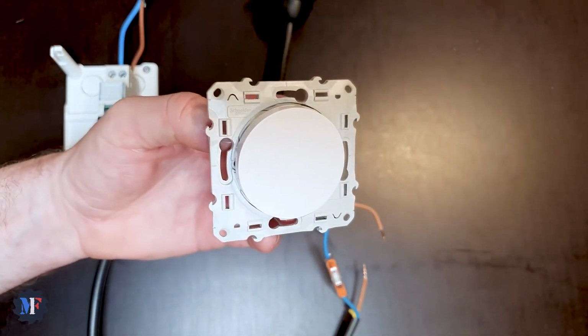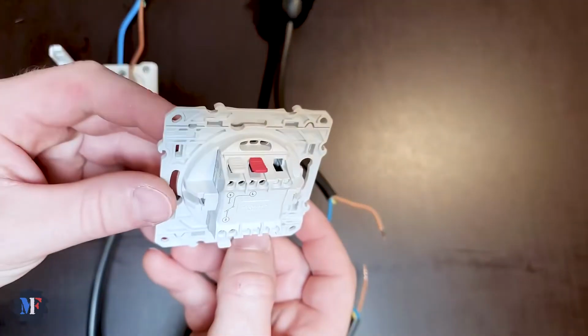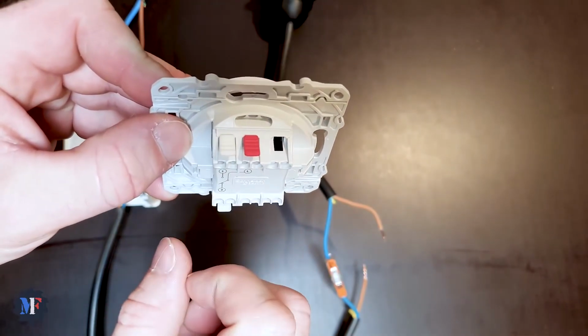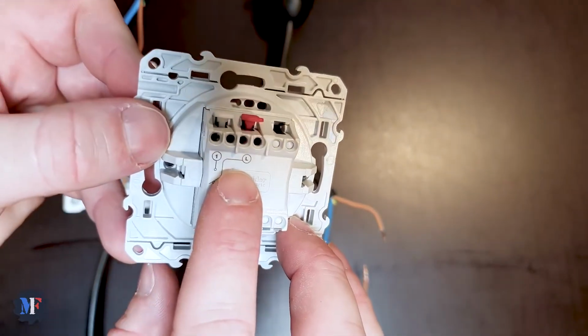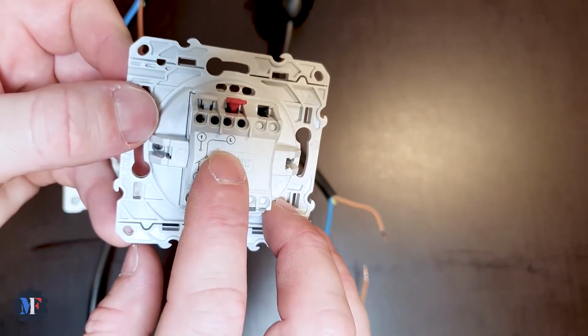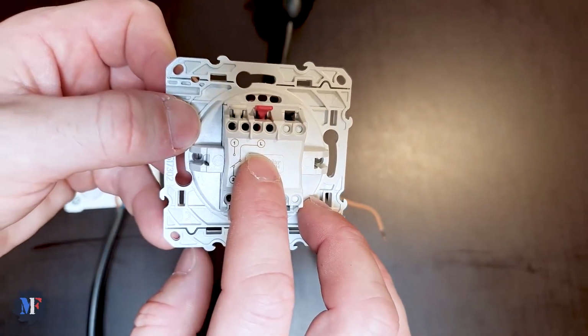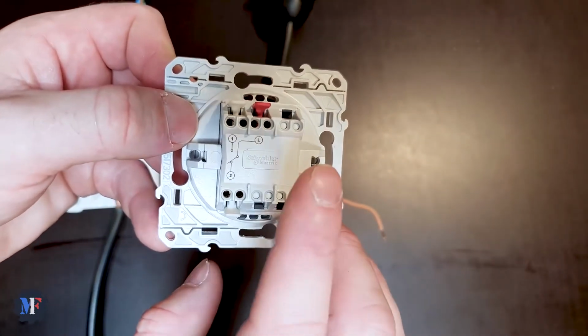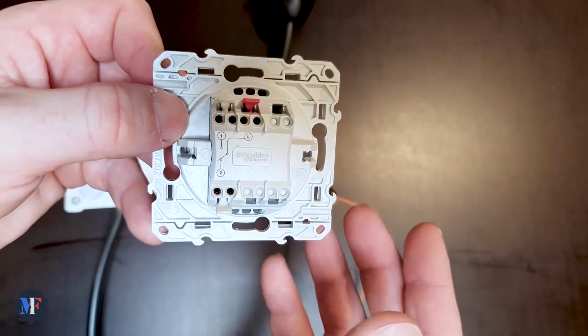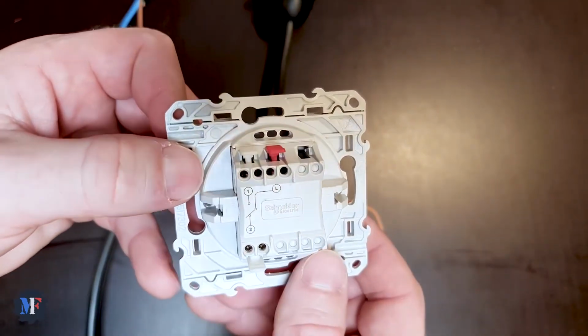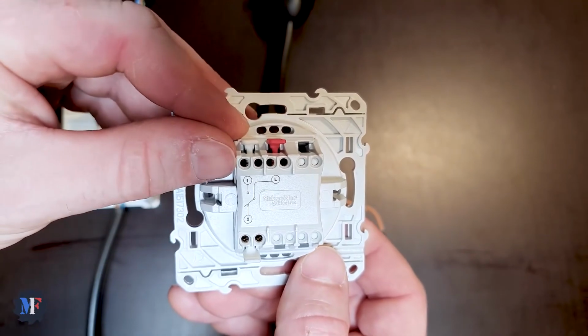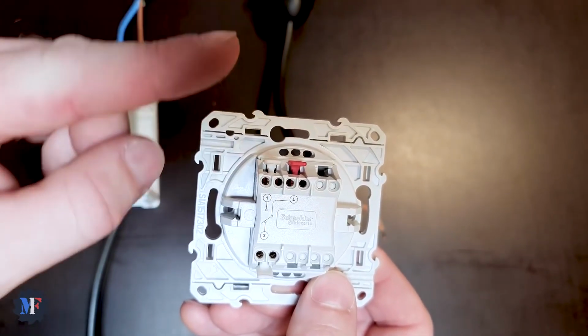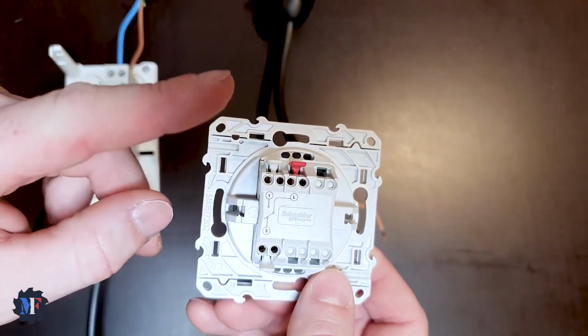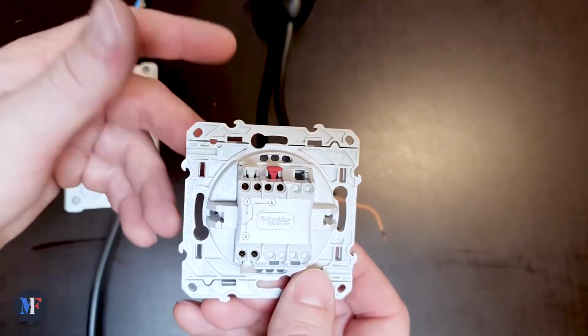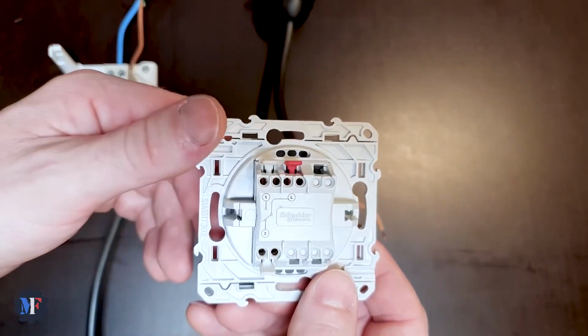We take a switch, Legrand, Schneider, whatever. On the back, the line terminal is marked in red, you can't go wrong, there's an L underneath. L for live in English, meaning the live or hot line. They could have used P for phase but they prefer English, that's how it is. Number 1 will be the wire that directly connects the switch to the bulb, and number 2 we'll see later when we have a second switch to connect.